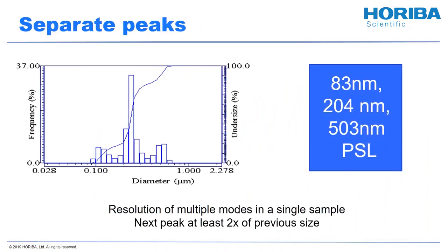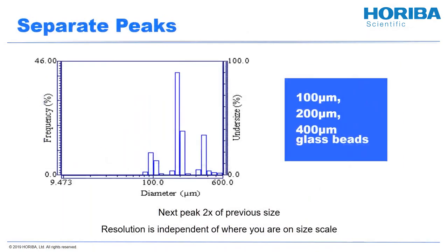If my peaks are more widely separated — for example 83 nanometer, 204 nanometer, and 503 nanometer polystyrene latex — then I can resolve multiple modes in a single sample and see three distinct peaks. These peaks are about a two-to-one ratio in particle size, so they are well separated. The previous example had a difference of about 1.1x, and the wider separation lets you see distinct peaks in laser diffraction. That rule of thumb holds for glass beads at 100, 200, and 400 microns as well. It's really the ratio of peak sizes that gives you an estimate of how well you can separate things.